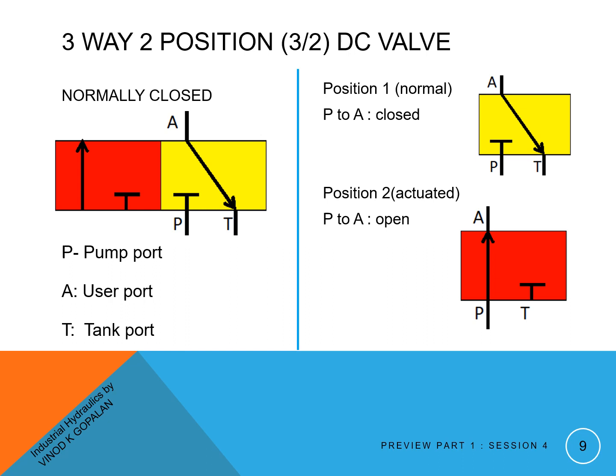P is the pump port, A is the user port, and T is the tank port. Since there are three service ports, it's a three-way valve - two positions and three ways. So it's called a three-way two-position, or in short, 3x2 DC valve.